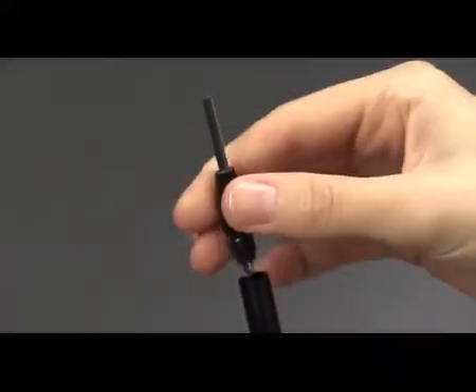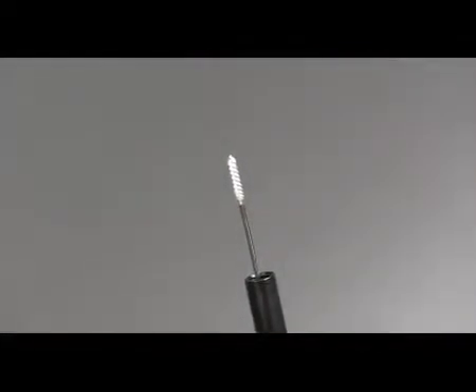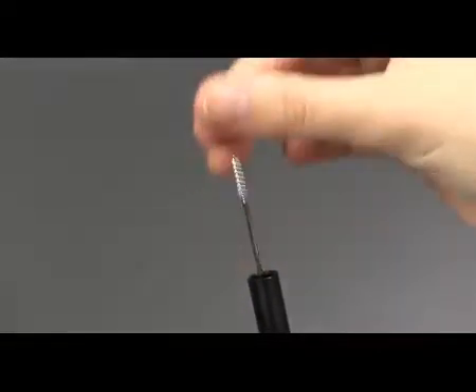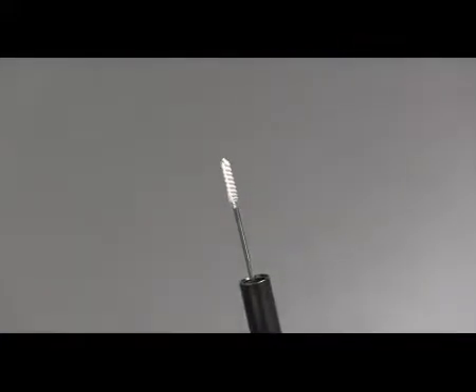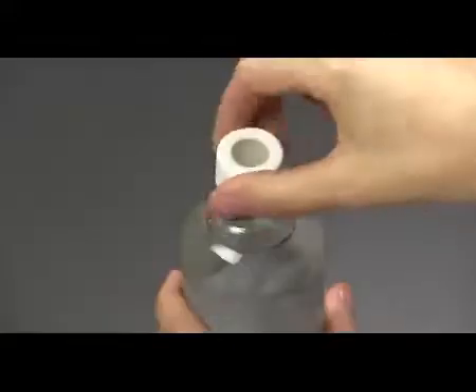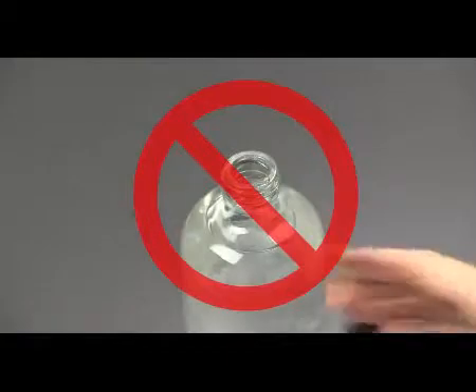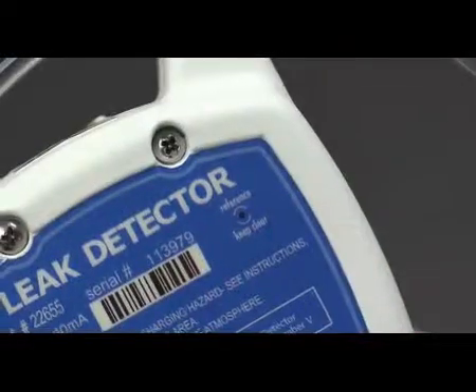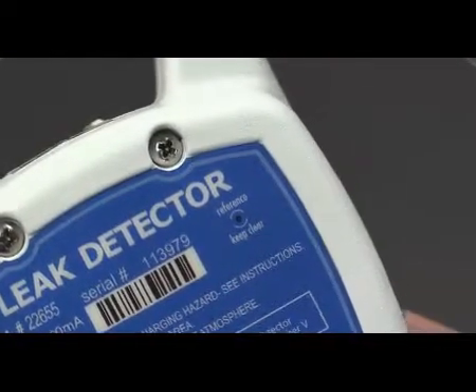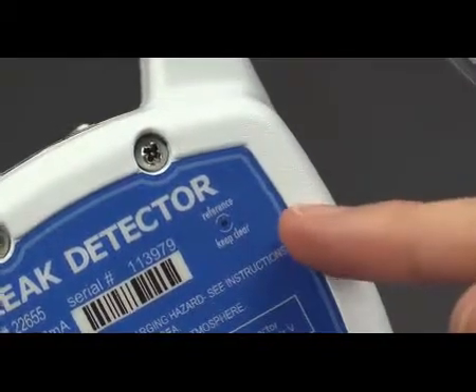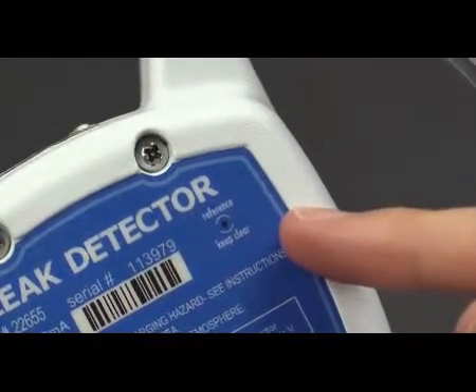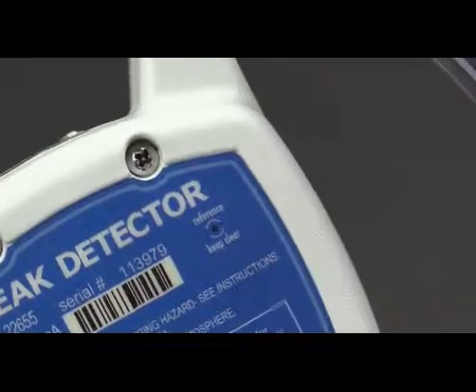To clean the probe tip, unscrew the cap to expose the brush. Gently clean the probe using a small brush or your fingers to remove dust and debris, and then replace the cap. Do not use liquids to clean the probe. You should also avoid setting your leak detector down near dust or other particles that can be pulled into the reference gas inlet on the back side of the unit when it is operating.